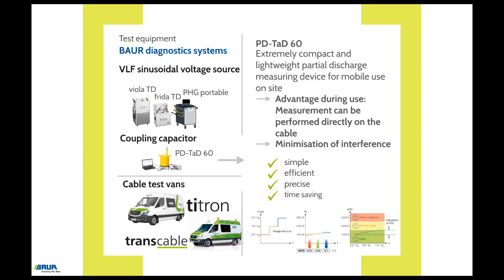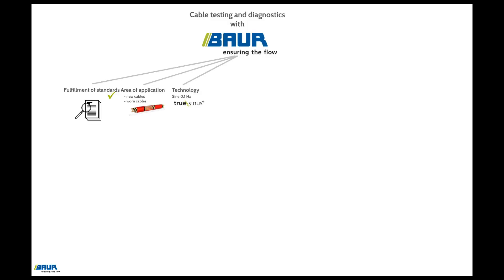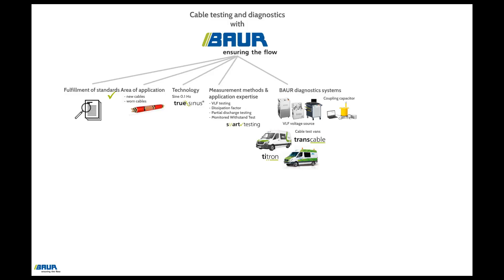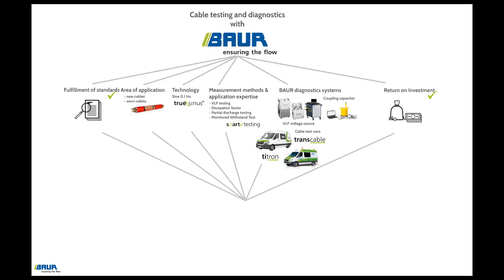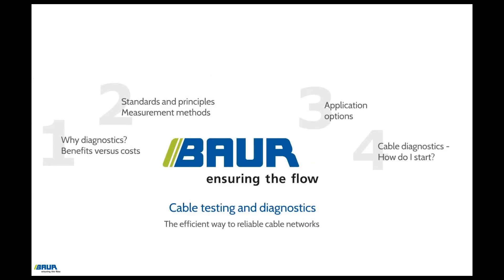This means that the cable only has to be loaded with the test voltage once. To sum up, cable testing and diagnostics with BAUR measuring devices can be used for the testing of both new and worn cable routes, whilst adhering to all relevant standards. 0.1 Hz sinusoidal voltage offers optimal preconditions for the use of VLF, dissipation factor measurement, and partial discharge testing, and for the combined variant, the monitored withstand test. The measuring equipment ranges from portable variants to integration in the transcable or titron cable test vans. The systems from BAUR permit precise and efficient cable testing and diagnostics for fault-free and reliable cable networks. The fourth part of the video series will focus on the implementation of cable diagnostics during operation and the presentation of practical examples.